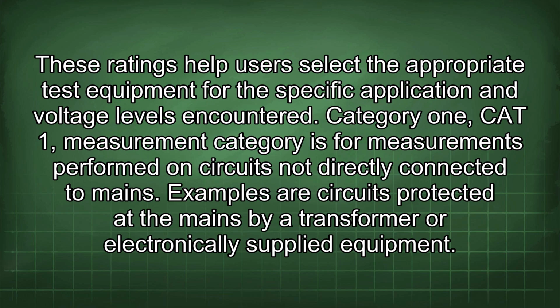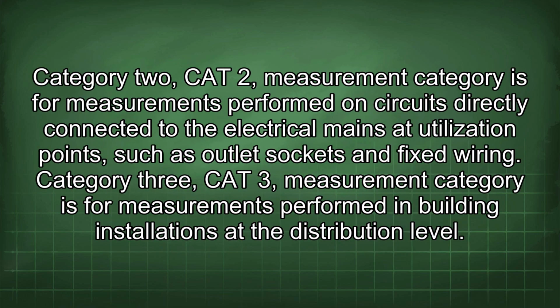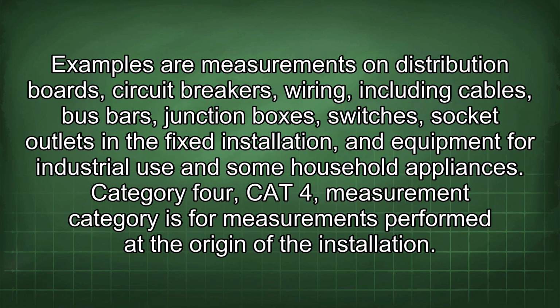Category 1, Cat 1, measurement category is for measurements performed on circuits not directly connected to mains. Examples are circuits protected at the mains by a transformer or electronically supplied equipment. Category 2, Cat 2, measurement category is for measurements performed on circuits directly connected to the electrical mains at utilization points such as outlet sockets and fixed wiring. Category 3, CAT3, measurement category is for measurements performed in building installations at the distribution level. Examples are measurements on distribution boards, circuit breakers, wiring, including cables, bus bars, junction boxes, switches, socket outlets in the fixed installation, and equipment for industrial use and some household appliances.